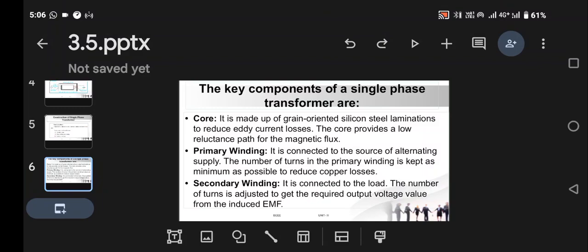The key components are, first, the magnetic core. It is made up of silicon steel laminations to reduce eddy current losses. The core provides a low reluctance path for the magnetic flux. The second component is the primary winding. It is connected to the source of alternating supply. The number of turns in the primary winding is kept as minimum as possible to reduce copper losses. Then the secondary winding is connected to the load. The number of turns is adjusted to get the required output voltage value from the induced EMF.